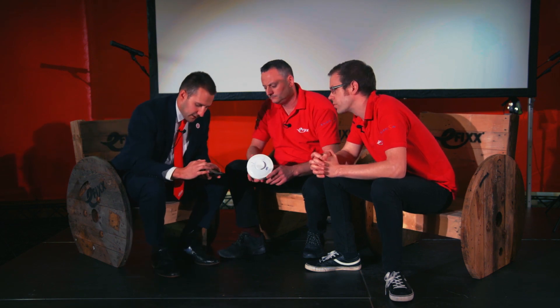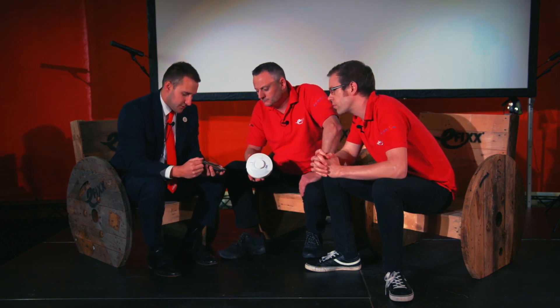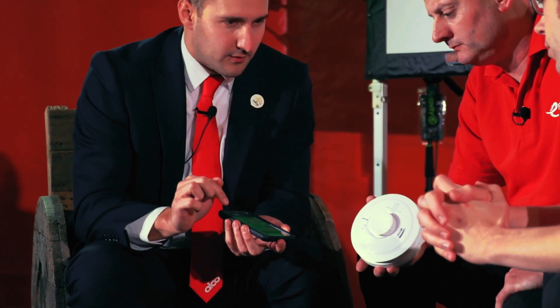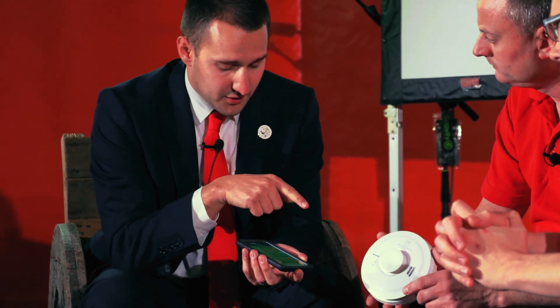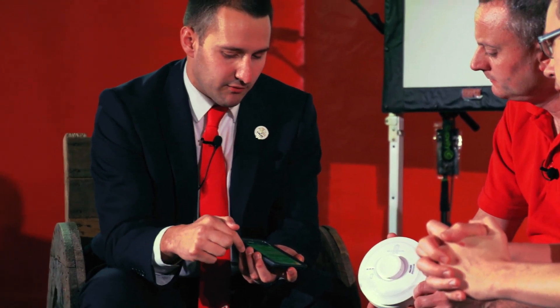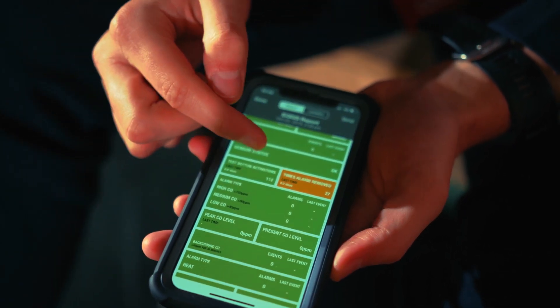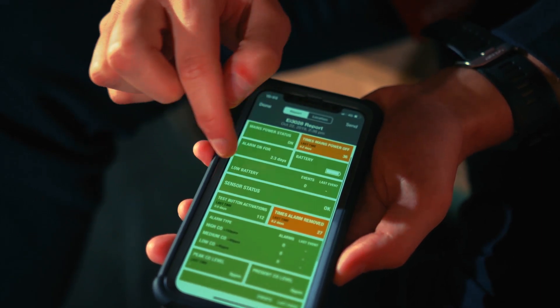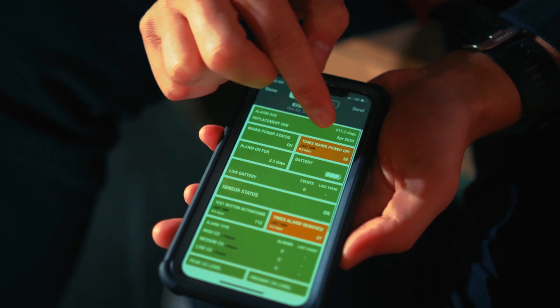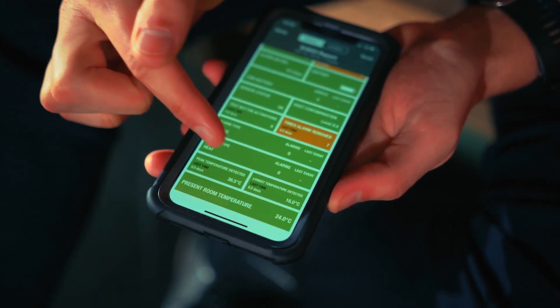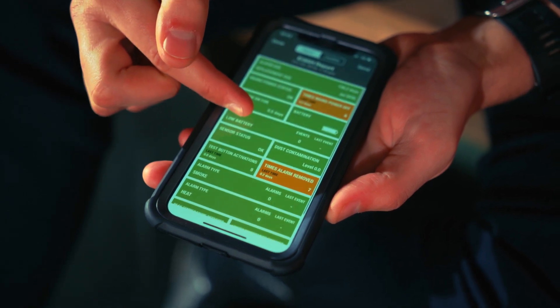Looking at the report, first it gives you the age of the alarm — we can see this one is due to be replaced in April 2030. It gives you the mains power status, any times the head has been removed, any times the mains power supply has gone off. It gives sensor information, any activations, any peak CO readings, any high temperatures — whatever the sensor is designed to detect, it shows you that peak or high reading.